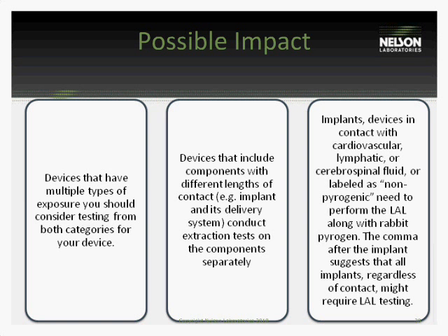But what the potential impact of that is, we base all this test off surface area. So the more surface area, the more volume we add. So if you're combining components of that device that do not have long-term contact with the device that does, then you're increasing the surface area of all the material there. So let's say some of that device that does not have long-term contact is non-toxic, but the one that has long-term contact is toxic. By increasing the surface area, you could be hiding those results. So this is why it's important to separate the two contact out, so that you're not hiding any toxic materials by increasing the surface area of safe materials.